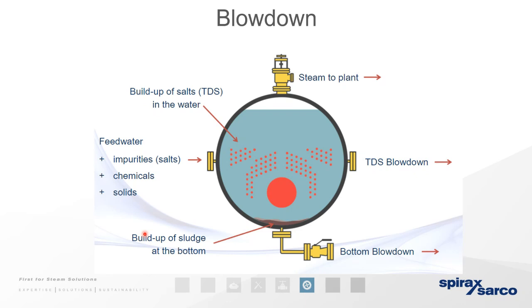Chemicals and minerals that are present in raw water itself, and the chemicals we add to the water, will behave in 2 different ways. Some will solidify and make the particles fall as sludge to the bottom of the boiler, and some will be held in suspension. So that's what we mean when we say total dissolved solids. So both of these we need to get rid of.